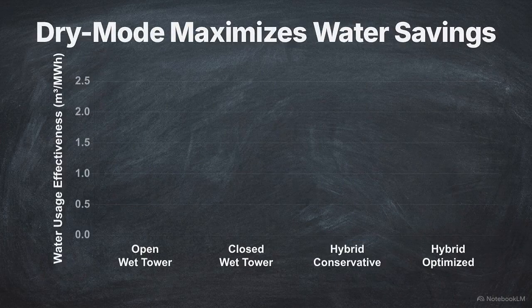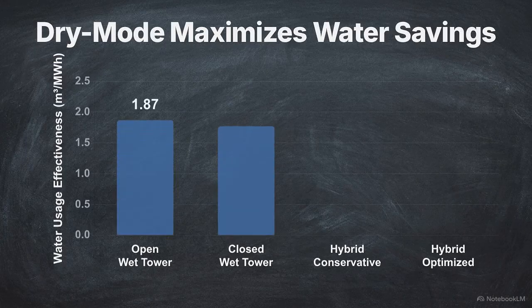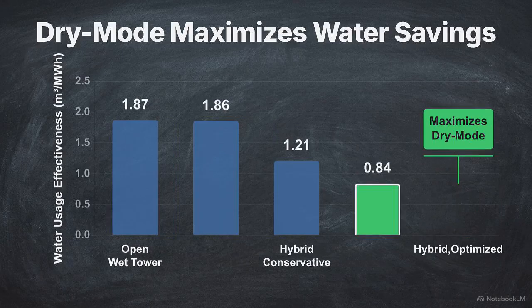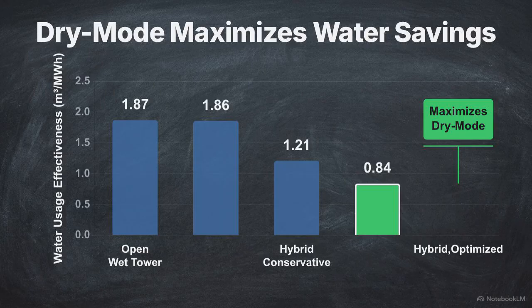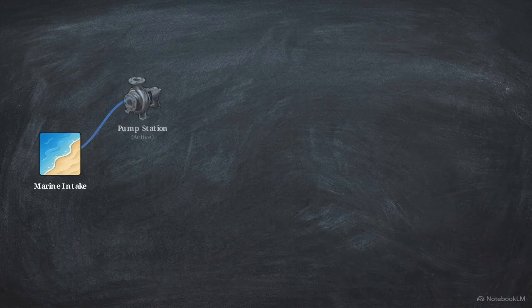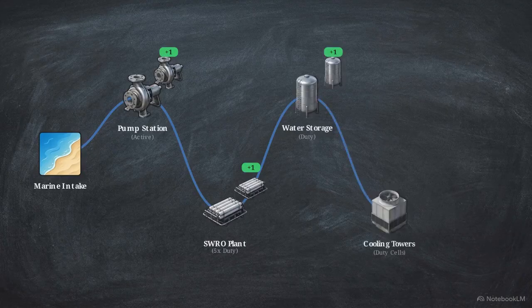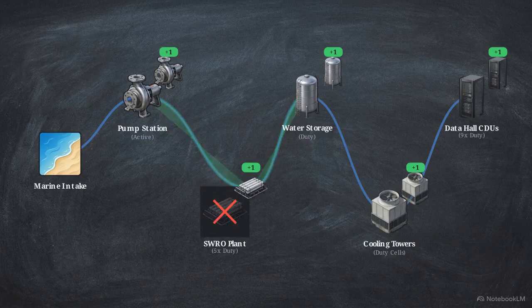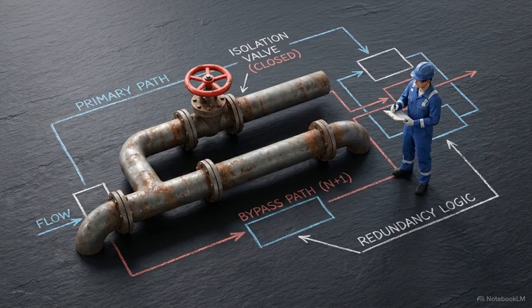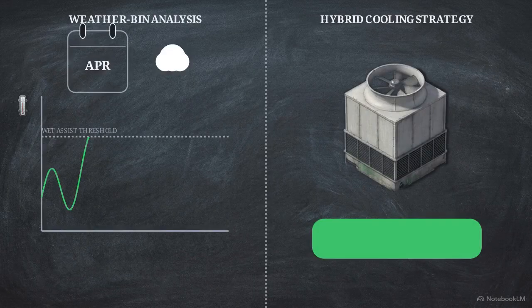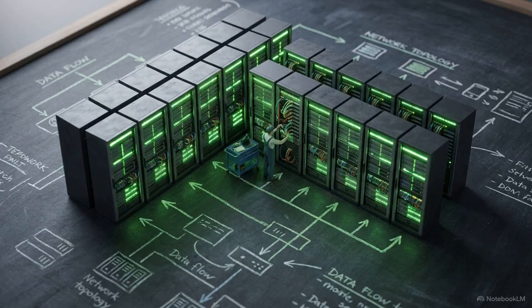Final performance is measured by water usage effectiveness, or WUE. Both open and closed wet towers operate at a baseline of approximately 1.87 cubic meters per megawatt hour. By slashing wet operating hours, an optimized hybrid system drives that metric down to 0.84. This reduction is achieved by maximizing dry mode operation. To meet Tier 3 or Rated 3 standards, every critical step, from the marine intake to the CDU secondary pumps, requires N+1 redundancy. One train or component must be isolatable for maintenance without interrupting the IT payload. Sustainability and reliability are validated together by confirming the reduction of wet hours through weather bin analysis, while maintaining the ability to isolate any part of the hardware chain.